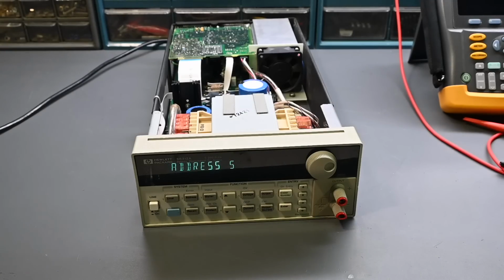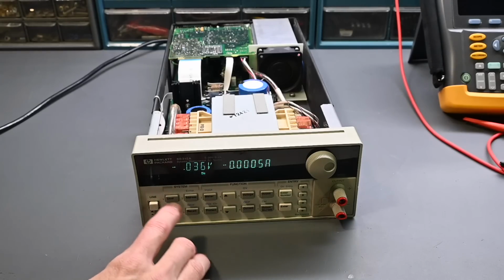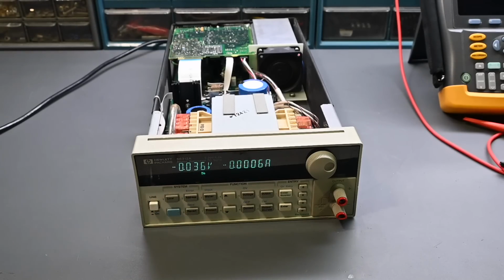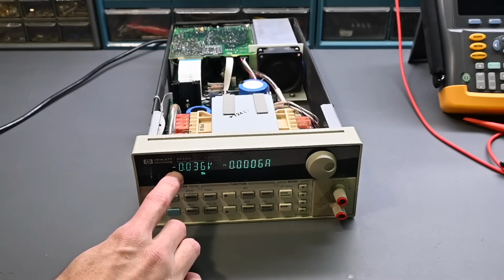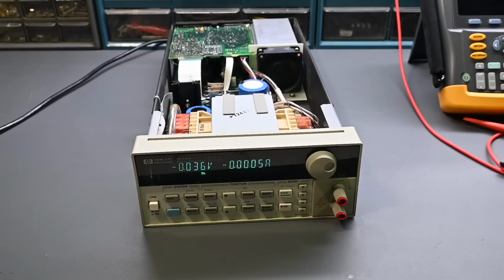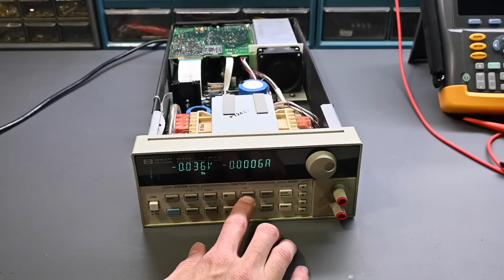So display self-test, the address, and then normal display. Perfect, good so far. Again, it's normal to see some small value shown on there, and then it says DIS for disabled. Also, something I noticed is that on the camera, the flickering you see on the display is exaggerated. It's not quite that way when I look at this. This display digit over here is flashing just slowly, but on the camera, it makes it look like it flickers a lot faster. All right, so let's set the voltage here.